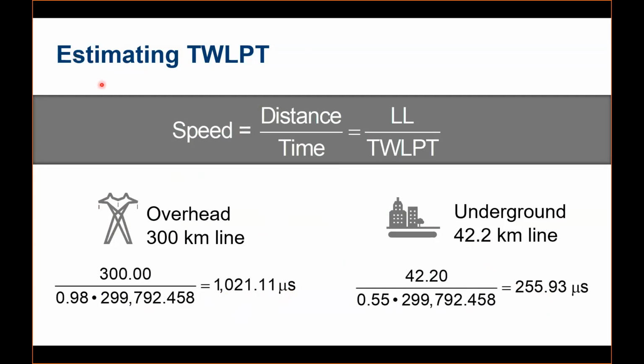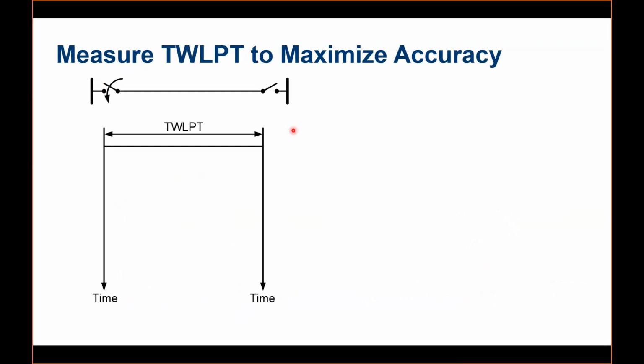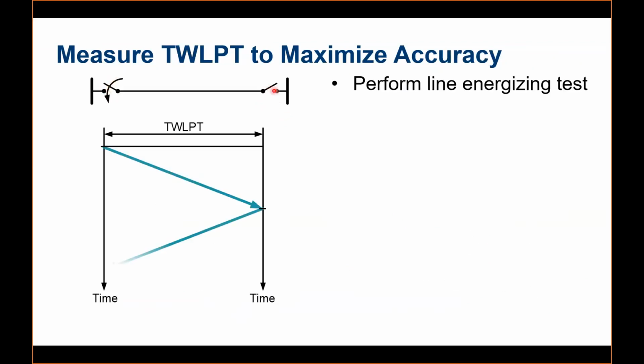We can calculate it. There's another way that we recommend, which is to actually measure the traveling wave line propagation delay. We call this a line energization test. So we do a test on the line. We open the remote breaker and try to close the local breaker. Once you close your local breaker with the remote breaker open, it will create a traveling wave because there is a switching action. The line is getting energized, it will be getting some currents and voltage as well. So there will be a disturbance, or a traveling wave will be generated over here.